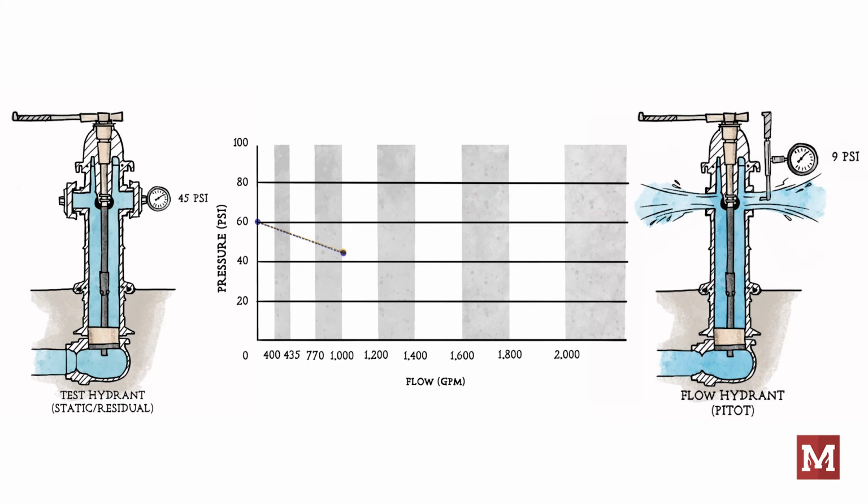So let's say we've got that OH1 system demand of 800 GPM, which before, because of our mismeasurement, we had an impact of 3.4 psi or 7% error. But now, because we flowed more water, we're only off by 0.6 psi or just over a 1% error. That's far less error than when we flowed a small amount of water. That shows up in our fire flow calculation as well. Our fire flow estimates improve substantially.